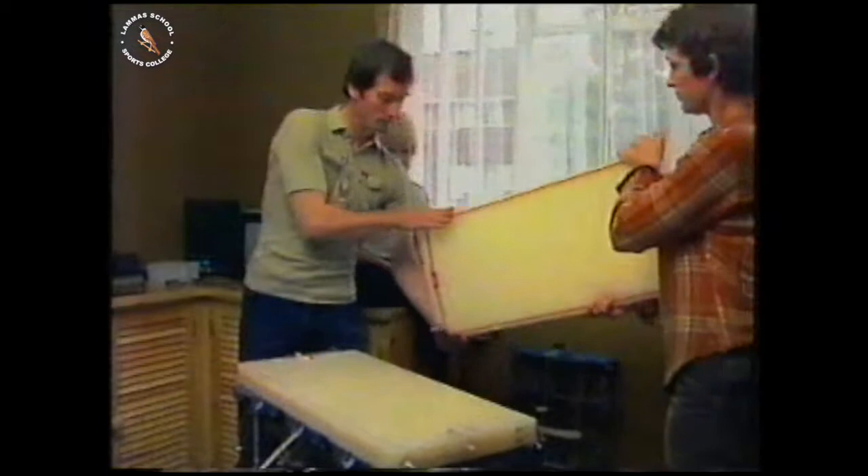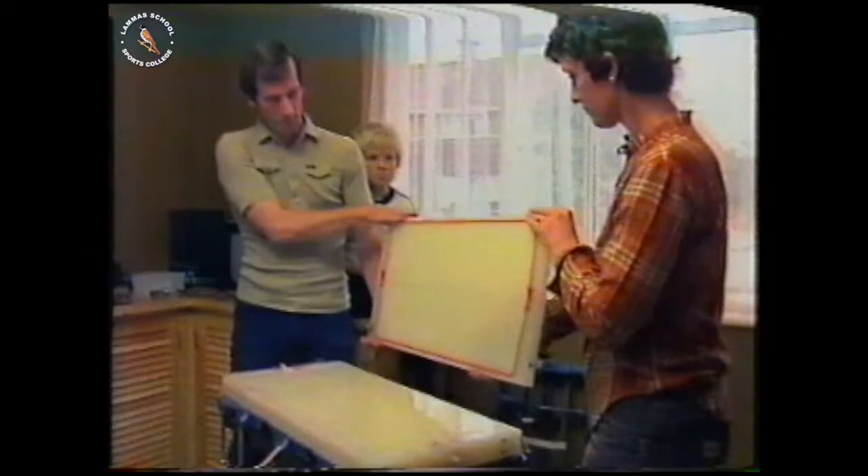To complete the kidney, another slab of plastic has to go on top. Each plastic slab is specially designed to allow the liquid dialysate to flow between it and the cuprophane sheets. This particular kind of kidney can be used over and over again, unlike the one in the hospital, but it has to be rebuilt every week.